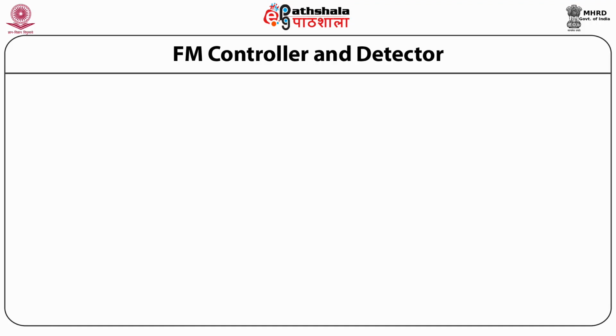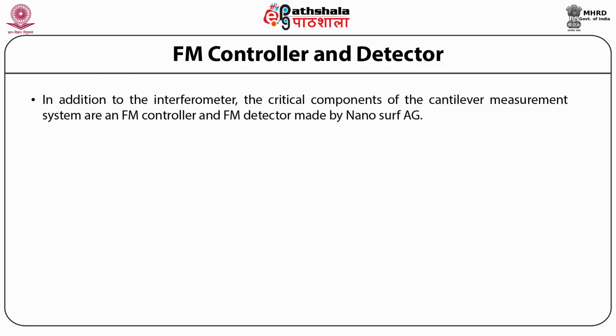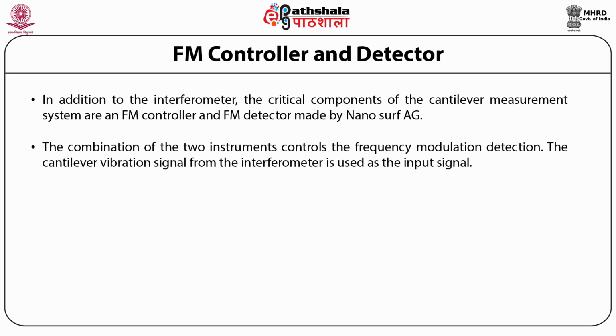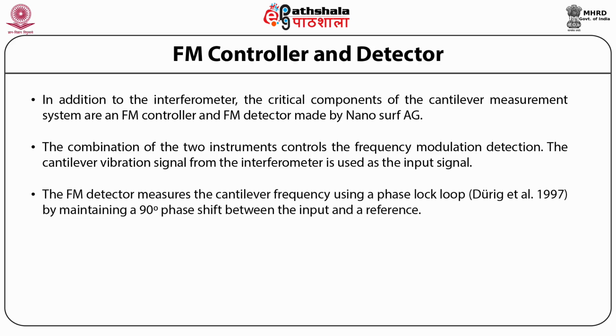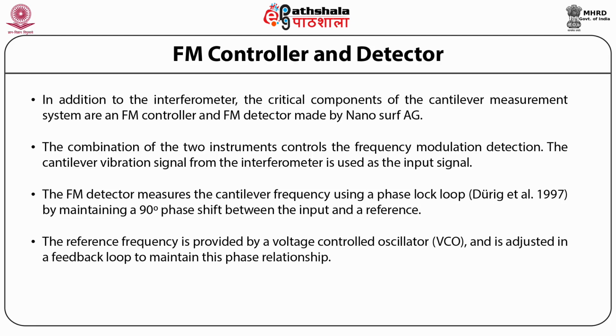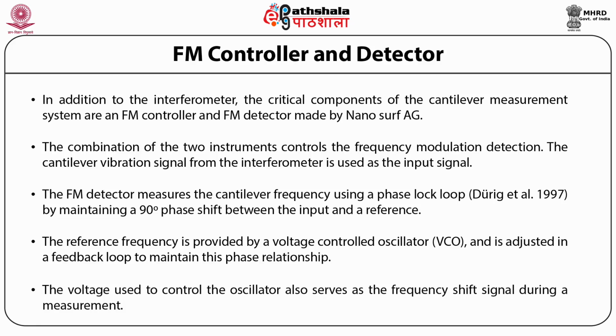FM controller and detector. In addition to the interferometer, the critical components of the cantilever measurement system are an FM controller and FM detector made by Nanosurf AG. The combination of the two instruments controls the frequency modulation detection. The cantilever vibration signal from the interferometer is used as an input signal. The FM detector measures the cantilever frequency using a phase lock loop by maintaining a 90-degree phase shift between the input and the reference. The reference frequency is provided by a voltage controlled oscillator, VCO, and is adjusted in a feedback loop to maintain this phase relationship. The voltage used to control the oscillator also serves as the frequency shift signal during a measurement.